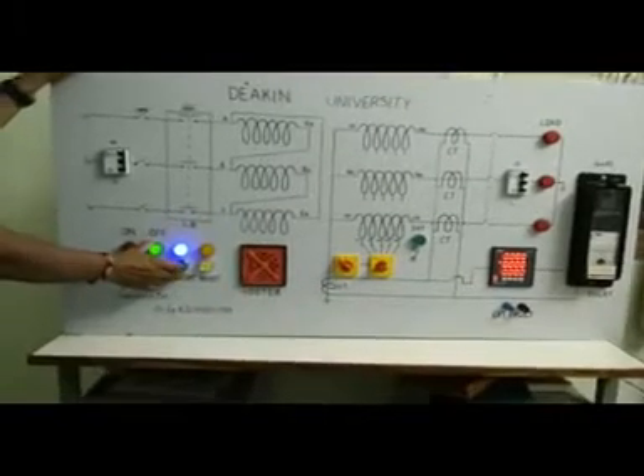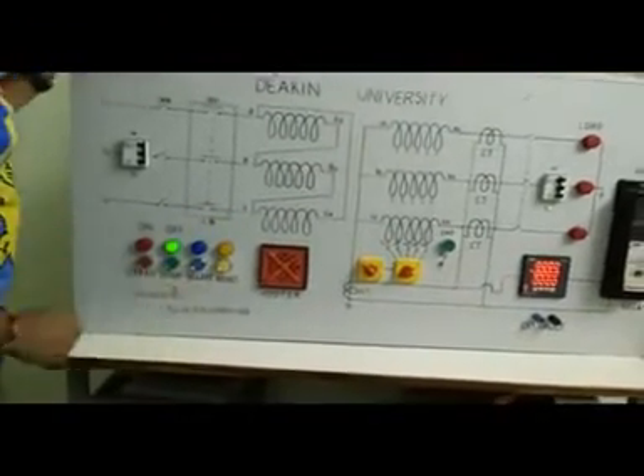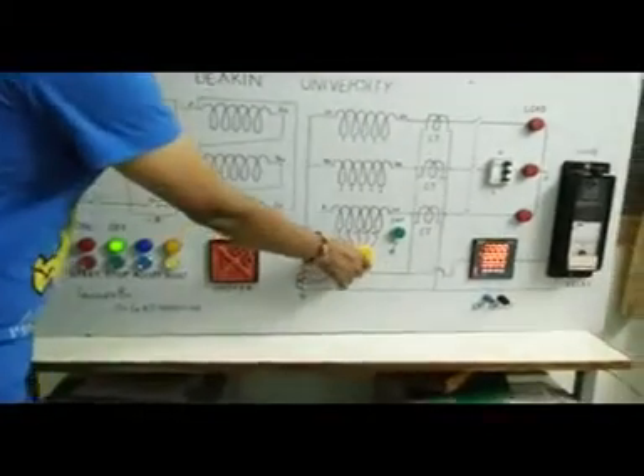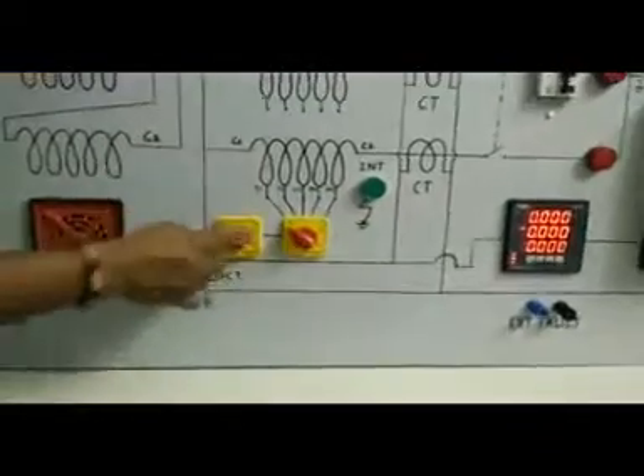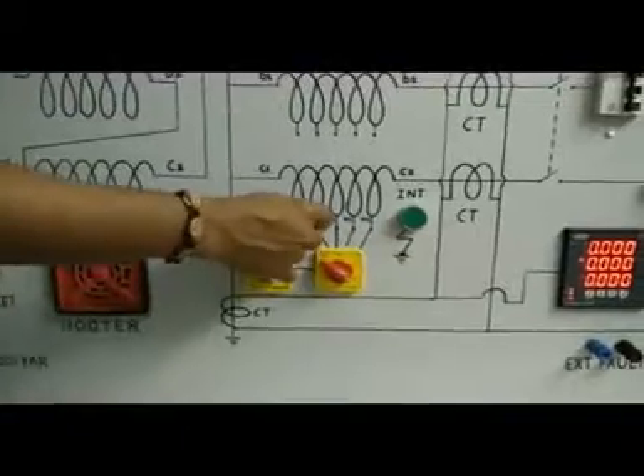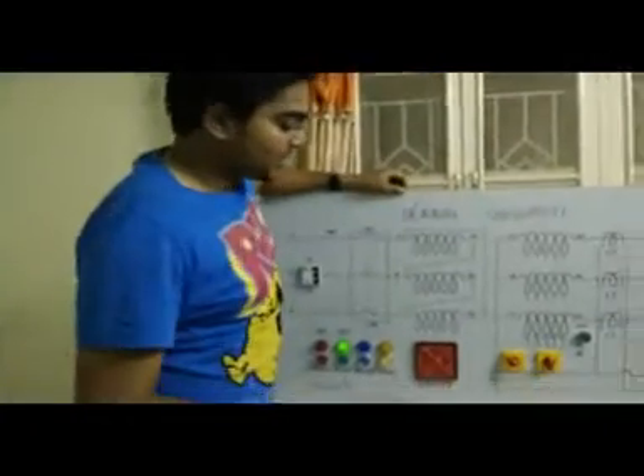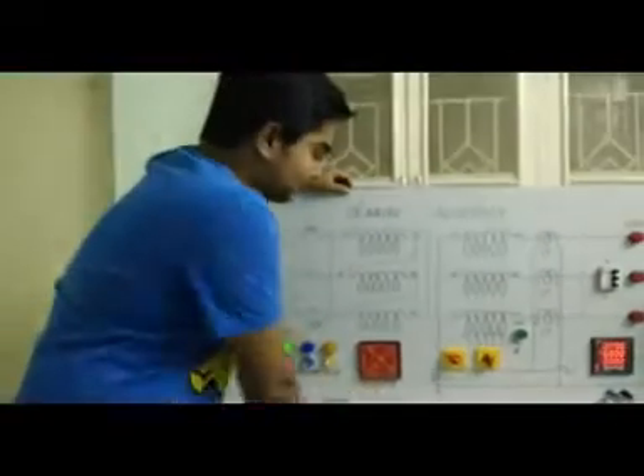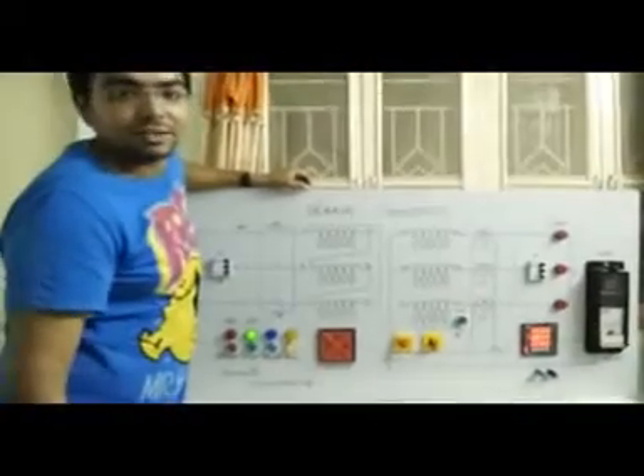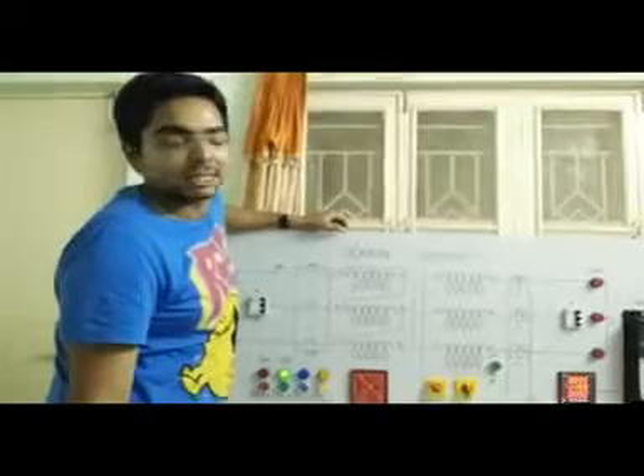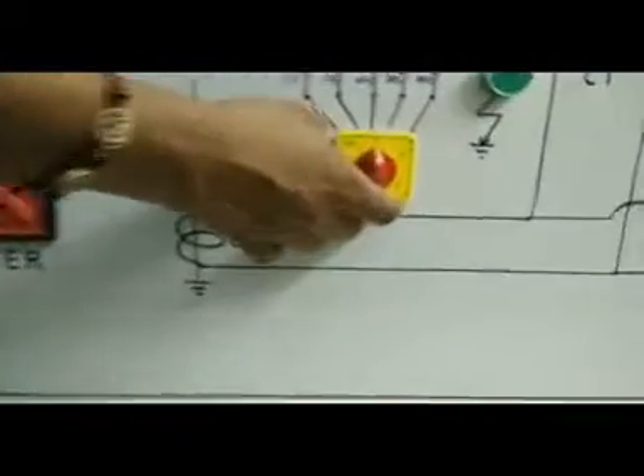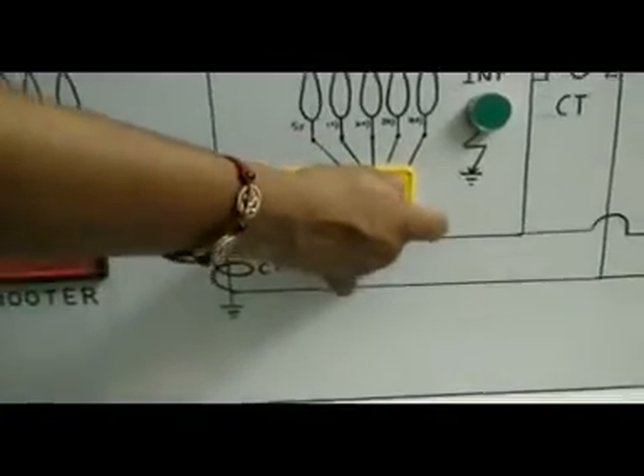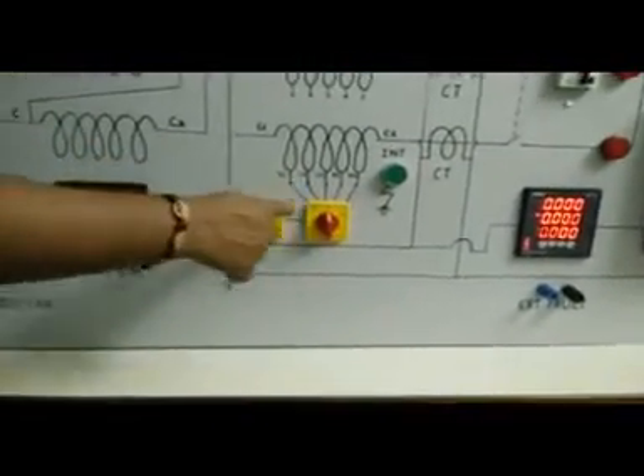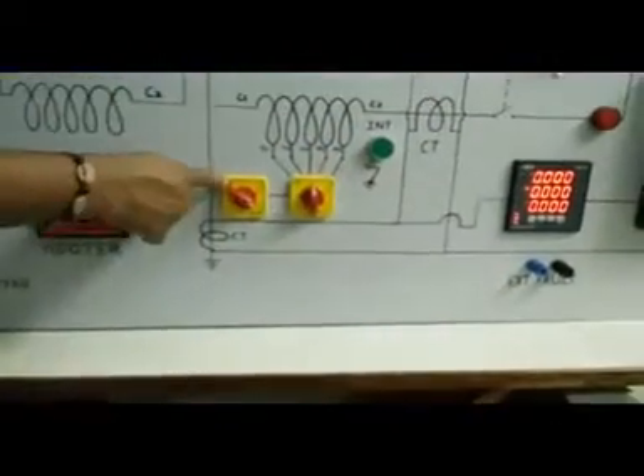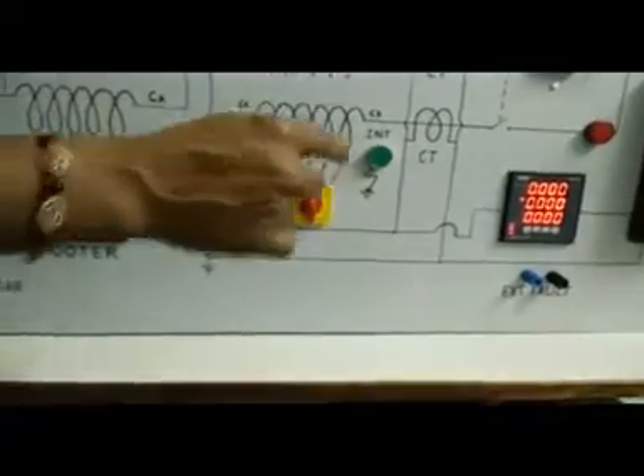Now we will stop the fault, and now we will select 20%. So now 20% of the winding is selected. In the last video I had shown the fault at 10%, but if the fault is very near to the earth, the fault current will be very small. So let's take the fault at 5% of the winding. At 5% of the winding, the fault current would be very small. And in this project, I will show the fault current at 5%. So when I generate the fault, you will be able to see the fault current over here. And this simulation will detect even that small amount of current.